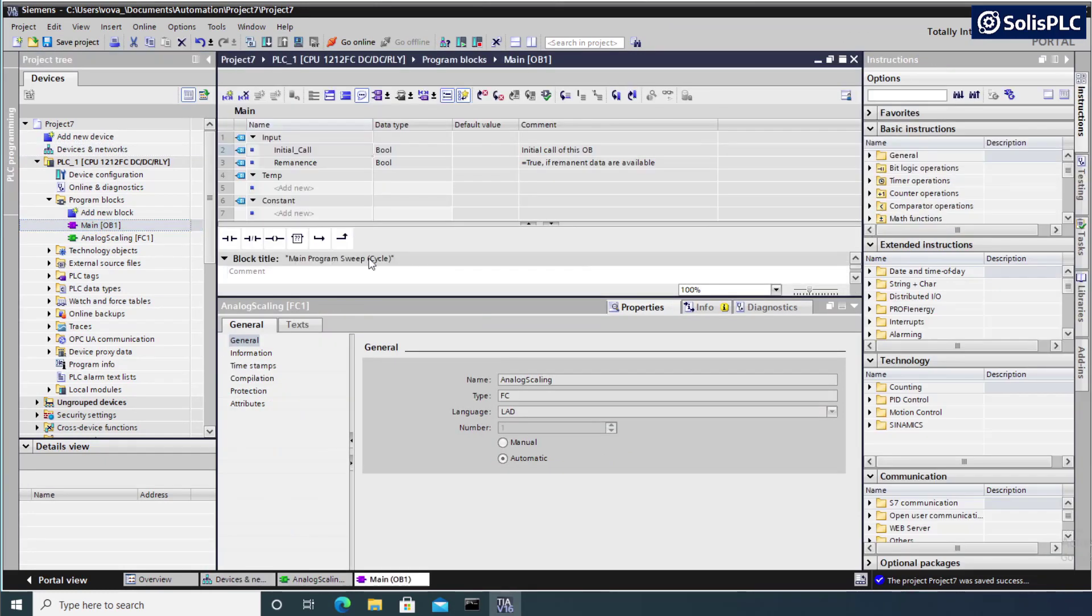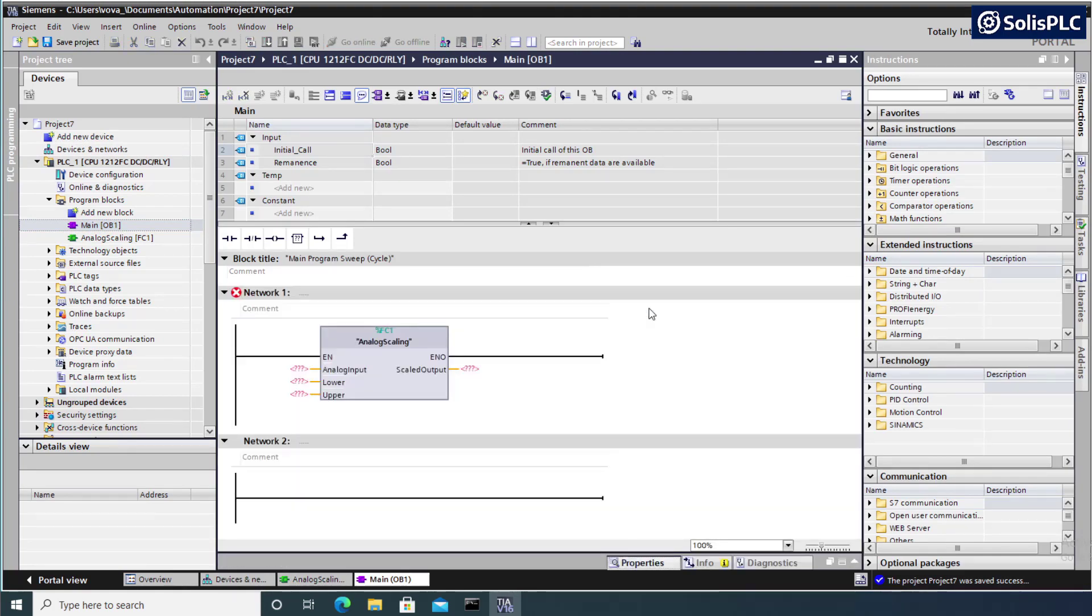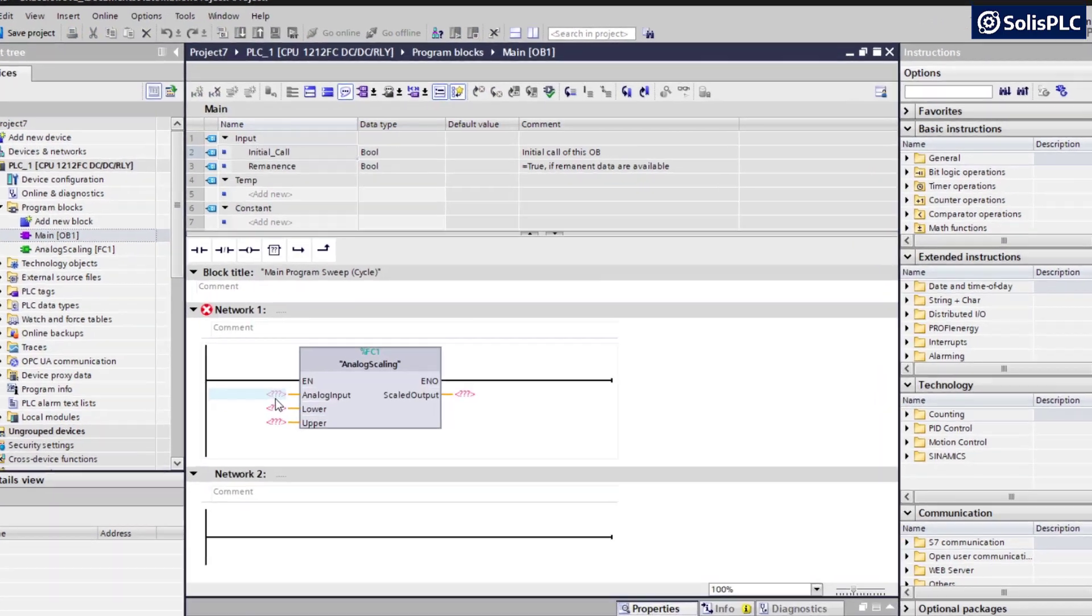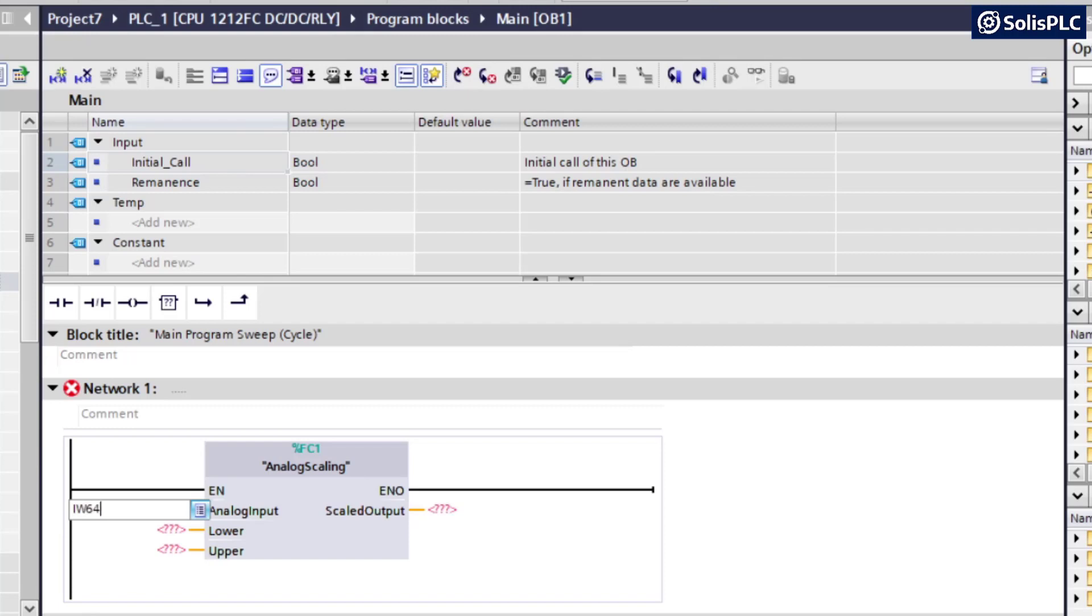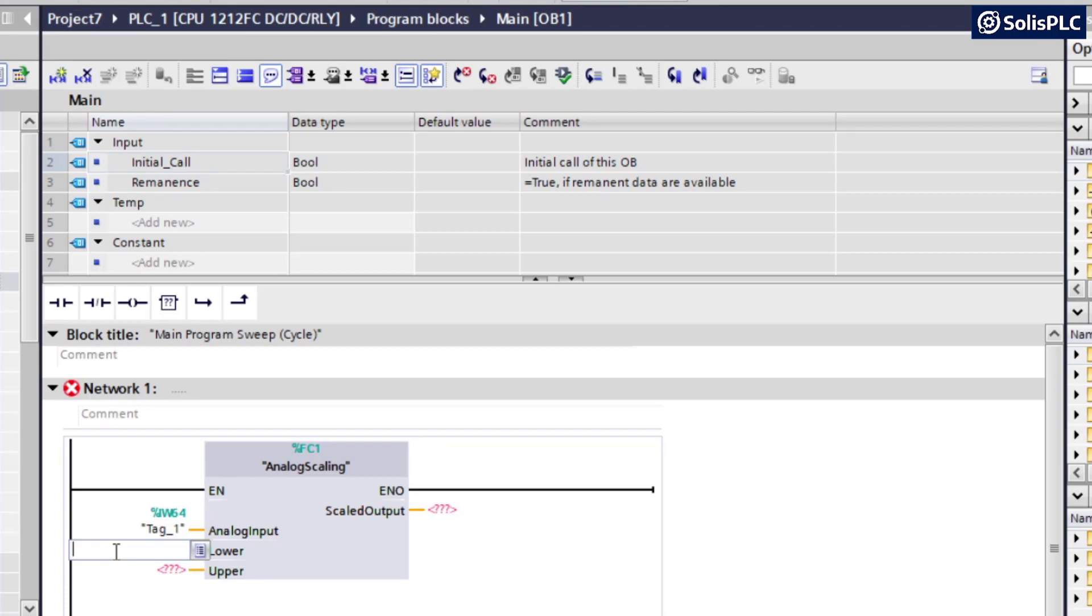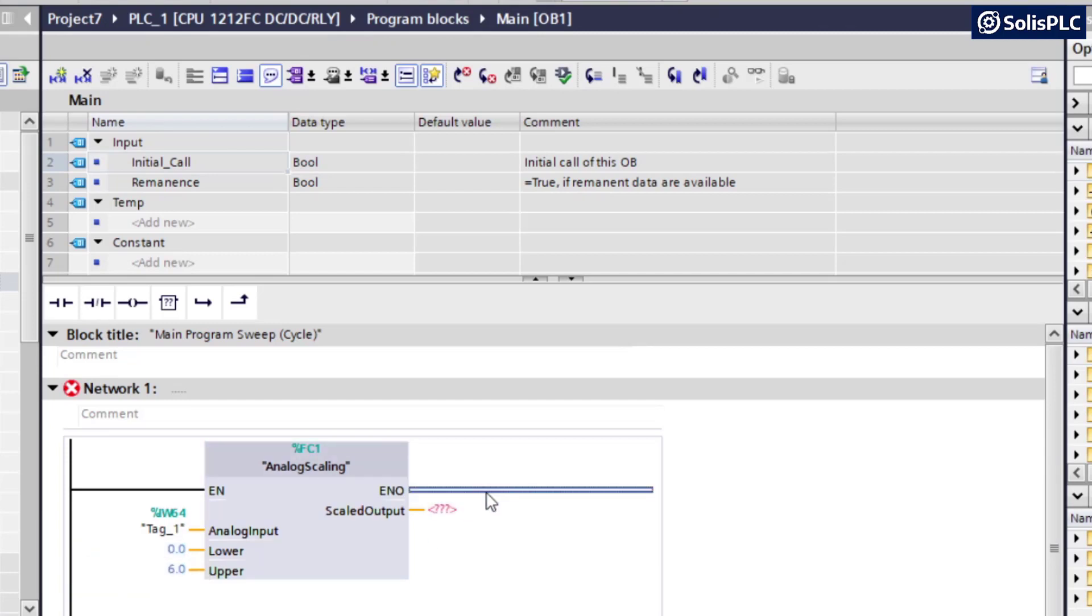So let's go back to main. I'm going to close this window for now. So IW64 is going to be our analog input number 0. The lower boundary, as I specified below, we can enter as a hard value or we can make tags for it. It's going to be easier to just enter 0 and our range sensor is going to go up to 6 meters.